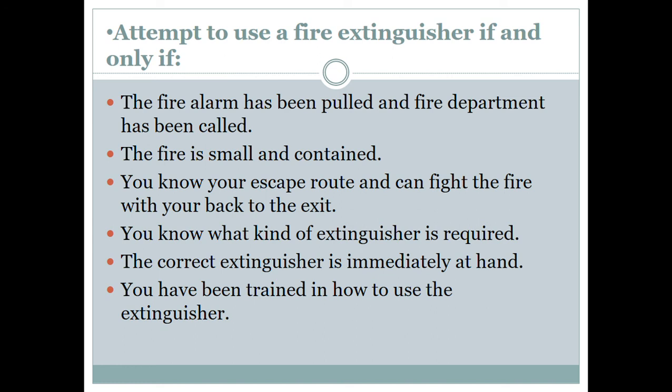Attempt to use a fire extinguisher if and only if: the fire alarm has been pulled and the fire department has been called, the fire is small and contained, you know your escape route and can fight the fire with your back to the exit, you know what kind of extinguisher is required, the correct extinguisher is immediately at hand, and you have been trained in how to use the extinguisher. These are the conditions that must be met when fighting a fire.